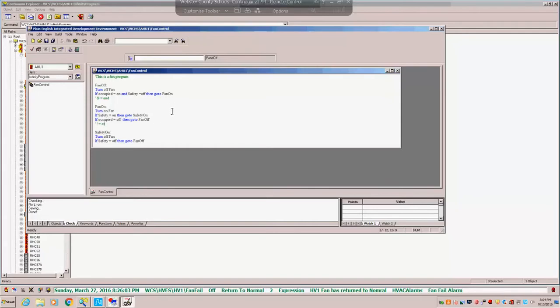There's another thing that timers are something you'll see quite often, so that you don't bang things on and off fast, on off pumps and fans and things. They don't like to be cycled on too quickly. Compressors, if you turn a compressor off, you like to have that off for a time. So there are time delays.